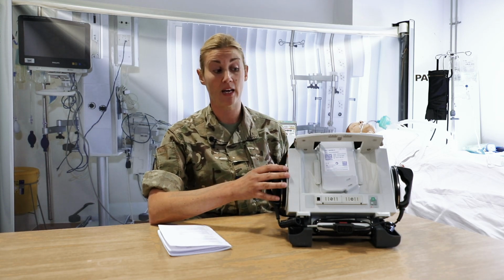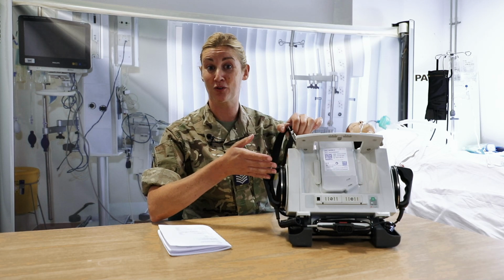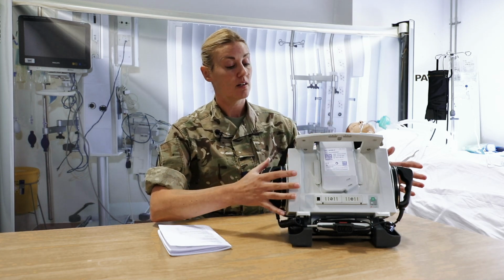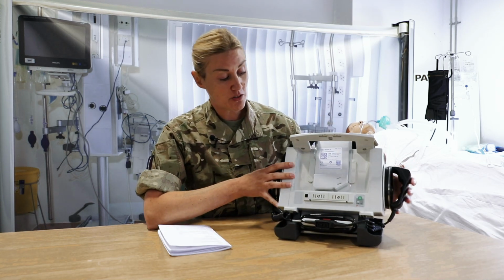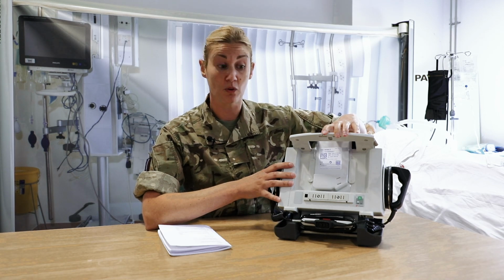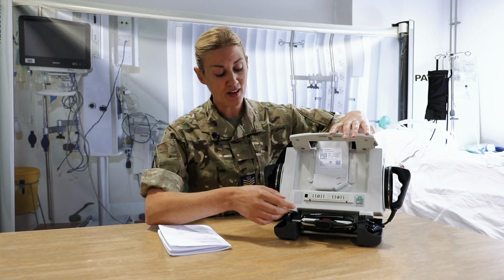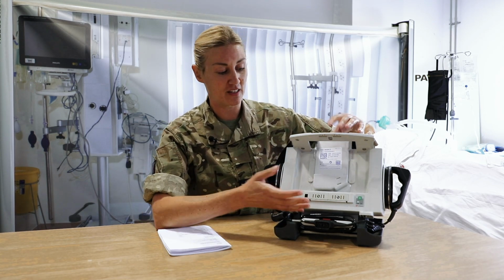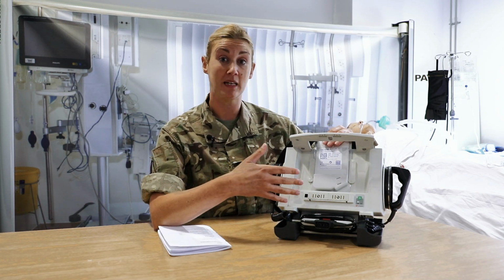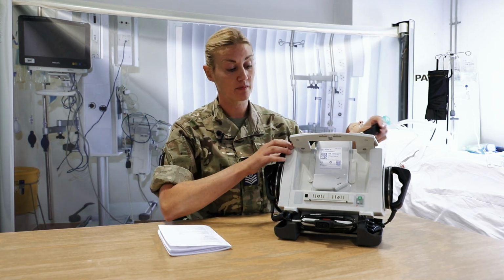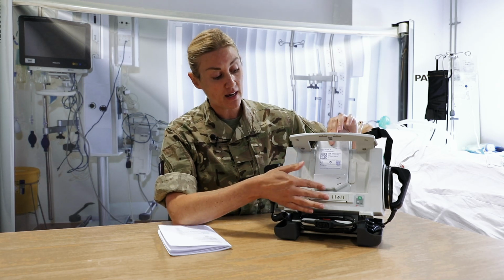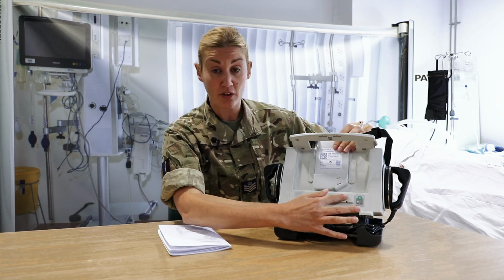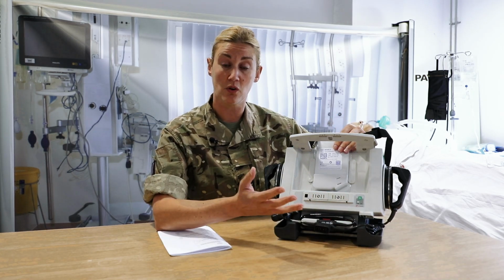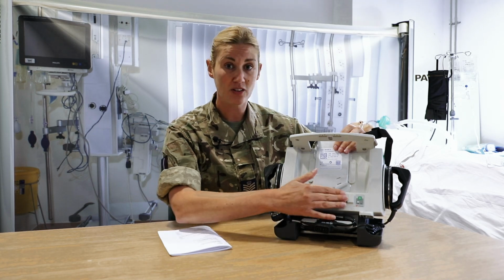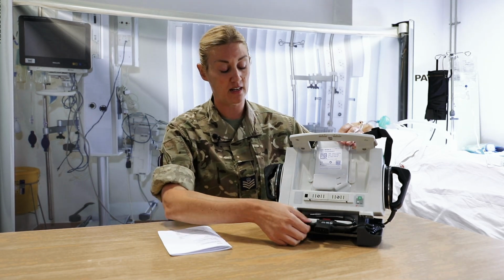But we will go through checking the paddles here because for this module, obviously they're connected. So again, dirt, dust and damage, we're going to go through and make sure that this all looks serviceable. We do have a bit of dirt on here, but obviously you could give it a bit of a clean. They're suitable to be cleaned with Clinell wipes if needs be. On the front here, we have an off and on button, and we've got those same connection ports that you saw on the back of the monitor. So again, just make sure that they're nice and clean and intact.